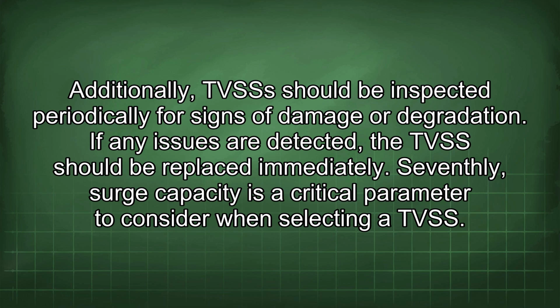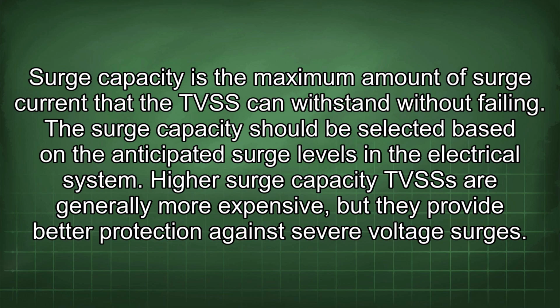Seventhly, surge capacity is a critical parameter to consider when selecting a TVSS. Surge capacity is the maximum amount of surge current that the TVSS can withstand without failing. The surge capacity should be selected based on the anticipated surge levels in the electrical system. Higher surge capacity TVSSs are generally more expensive, but they provide better protection against severe voltage surges.